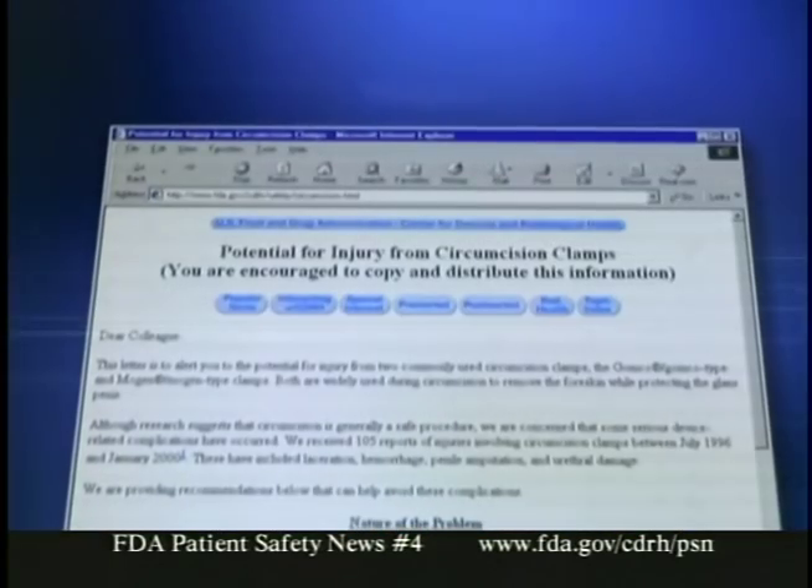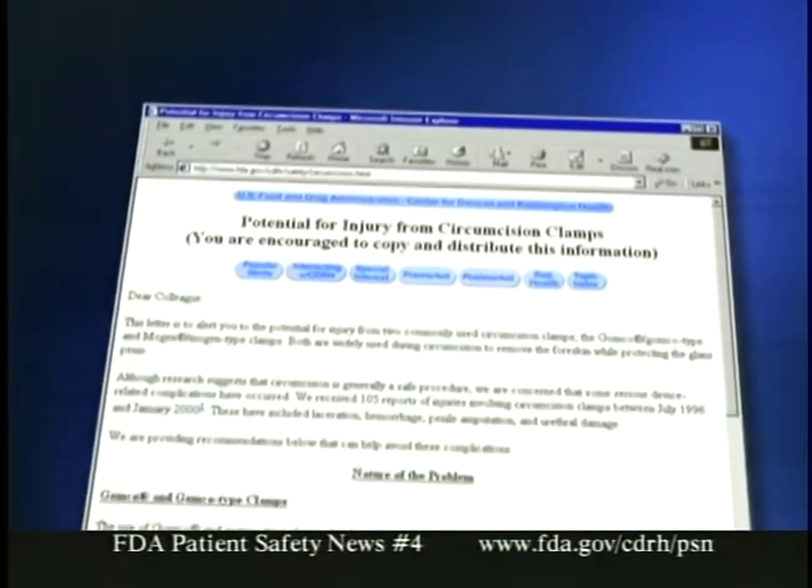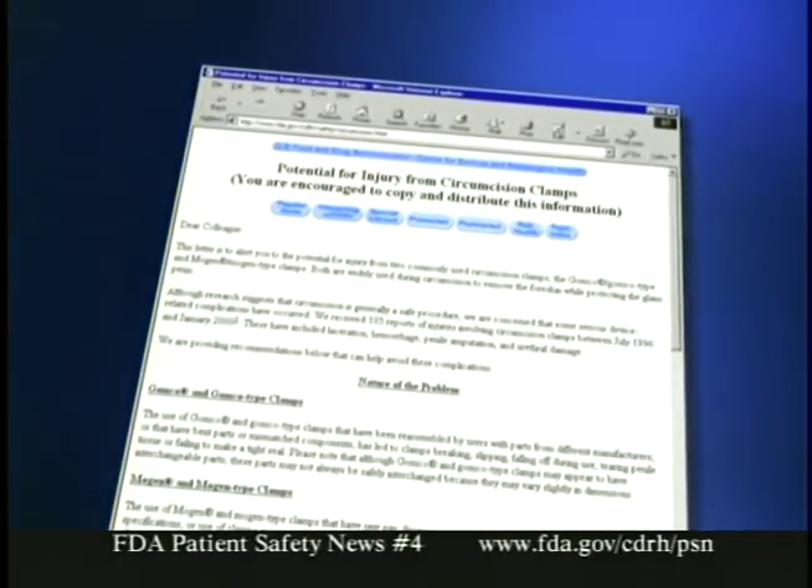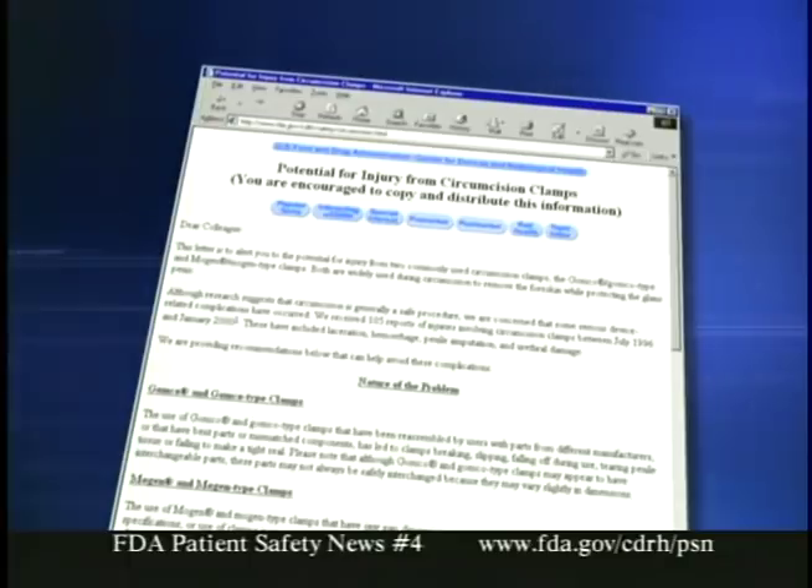In 1999, we issued a warning about the possibility of serious injury to patients from circumcision clamps. We were getting about 20 injury reports per year, including laceration, hemorrhage, urethral damage, and penile amputation. The number of reports has gone down since we issued the warning, but they continue to come in, and the injuries, rare as they are, continue to be serious. We want to remind you about steps you can take to avoid these injuries. The 1999 warning explained what can go wrong with two widely used types of circumcision clamps: the Gomco type and the Mogen type.